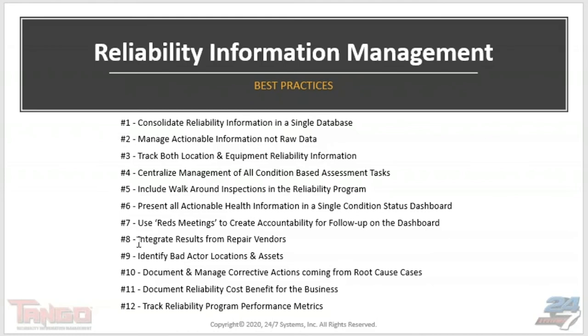Best practice number eight: provide a portal so that results learned by repair vendors become part of the reliability database. If you spend time in places like motor shops, it's amazing what you might hear from technicians doing teardown and inspection — recognizing the same motor coming back every six months, this time with windings filled with grease from over-greasing, causing overheating and premature failure again. Making it easy to capture that and allowing the vendor to database that information directly — rather than emailing a report that gets stranded — makes the data far more retrievable and mineable.